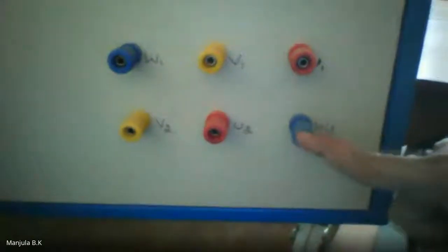see these are the knobs wherein the first load may take around 1 ampere. Similarly, if I switch on all the 5 loads, the maximum current it is taking is 5 amperes. If you look at the wiring diagram, what I have explained, it will have 3 coils, U1, U2, both indicated with red, V1 and V2, yellow, W1 and W2. So if I have to do the star connection, then I have to short all the 3 and get the star point. And IL and IPH have to be connected in line and phase. So this is about the setup that we have.